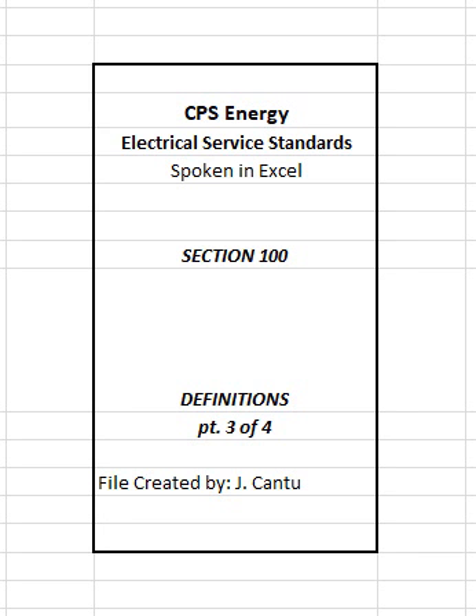C. Pad mount transformers. Where pad mount transformers are installed to serve commercial or industrial customers or high-rise residential buildings, the point of delivery will be at the secondary transformer spades, regardless of meter location. Exception. Where a tap box is required in accordance with Section 1000, the point of delivery will be in the tap box.